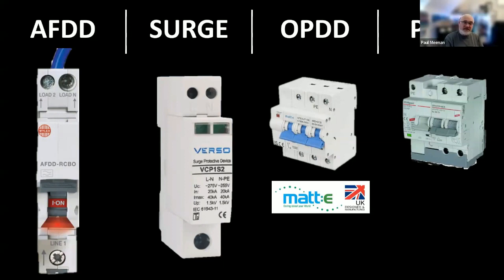So there's a device that's essential to earth. We now have the OPDD, which is soon to have a standard, and that's the open pen detection device. There's one that's been manufactured by a British company called Matt:e, and that looks for a supply neutral loss. So it's a device that effectively can protect against hazardous rises in voltages. That's something that's fairly new in the UK, and they have a whole suite of devices that can protect.